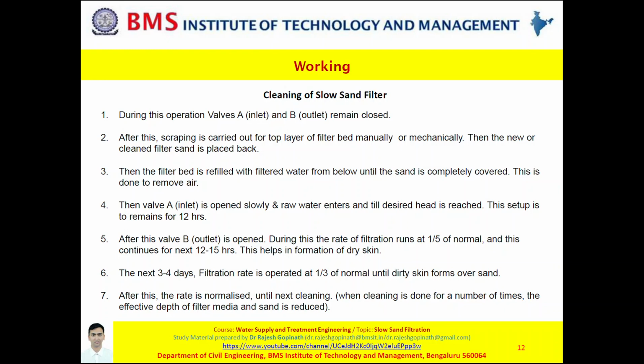As I told you before, the functioning of the slow sand filter is a combination of mechanical straining and the formation of dirty skin, which is biological metabolism. So after these operations have been done, which is 12 hours, again the next 12 to 15 hours, and the next 3 to 4 days, you may say that this total process takes 5 days.